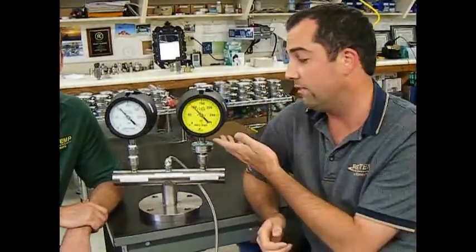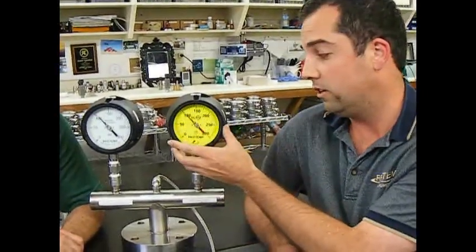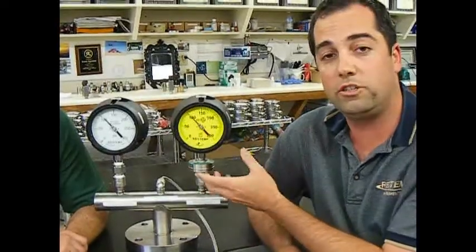with a water snubber on it, which helps dampen pulsation. On the left here you have the ReoTemp MS8 all-welded diaphragm seal gauge, which has your standard process gauge attached to a diaphragm seal, whose main role is to isolate the gauge from media that is either hot, corrosive, or clogging.